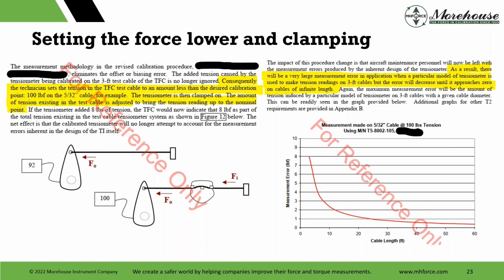The added tension caused by the 3-foot cable being calibrated is no longer ignored. So consequently, the technician sets the tension to an amount less than the desired calibration point, and then the tensiometer is clamped on. The amount of tension existing in the test cable is adjusted to bring the reading up to the nominal point. That is the method that replicates dead weight.